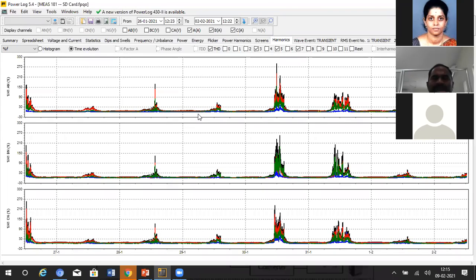This is a measurement we did on our campus. We do long-term energy and electricity parameter monitoring with a fluke meter. This is one particular week's data. During the daytime, from 6 a.m. to 6 p.m., you can see the harmonic level I've selected. Most days, during daytime, the harmonic level is beyond 30%, 40%, 70%, and sometimes even reaching 100% and above.